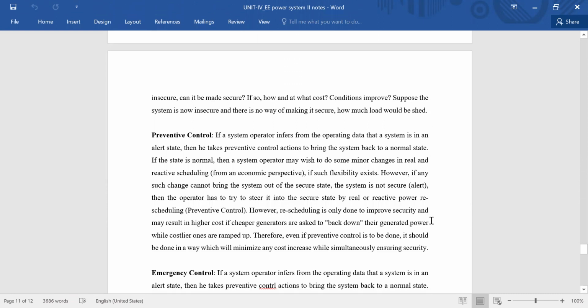Preventive control is when the system operator infers from the operating data that the system is in the alert state, so preventive control actions should bring it back to the normal state. In the normal state, the operator may wish to make minor changes in the real and reactive power scheduling, from an economic perspective.